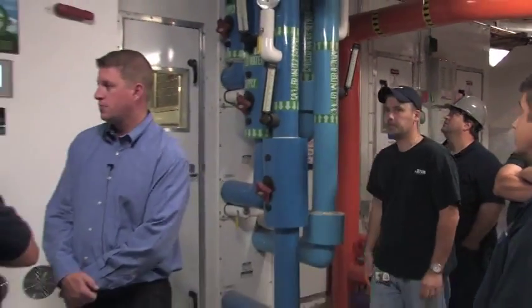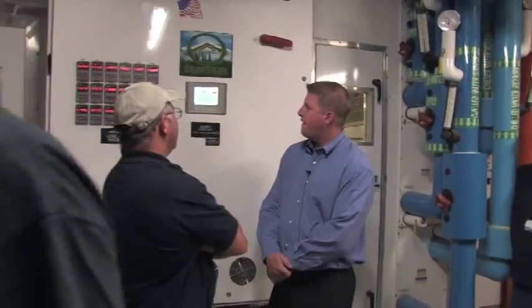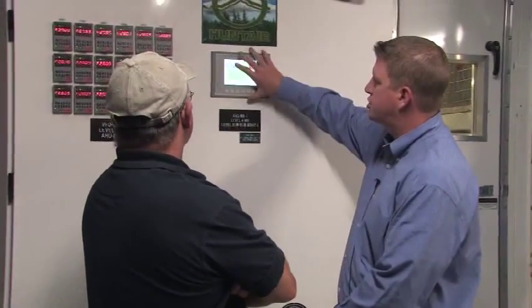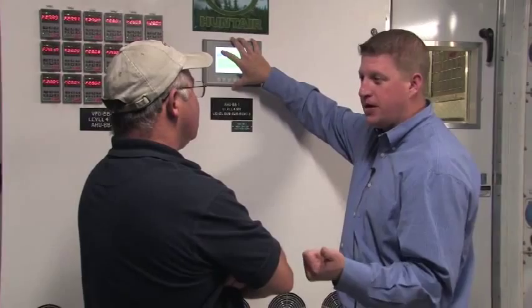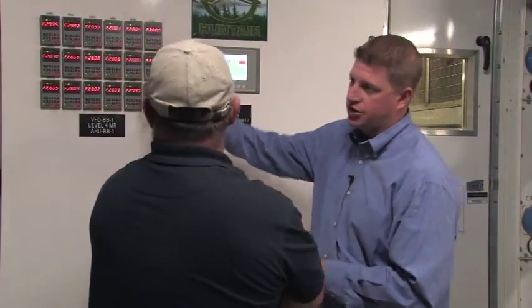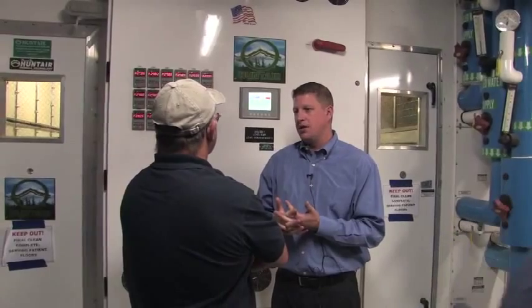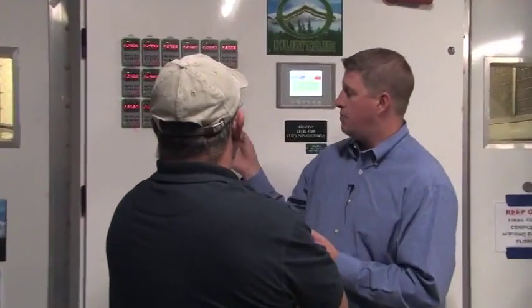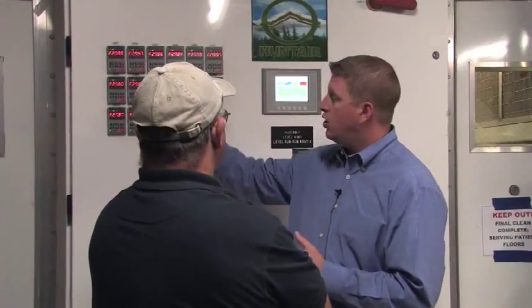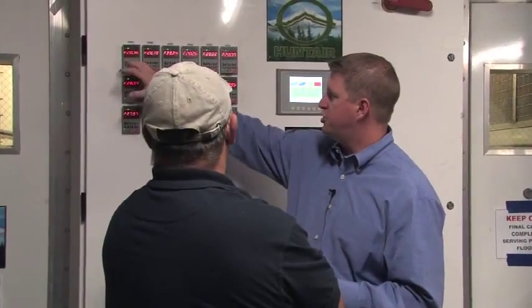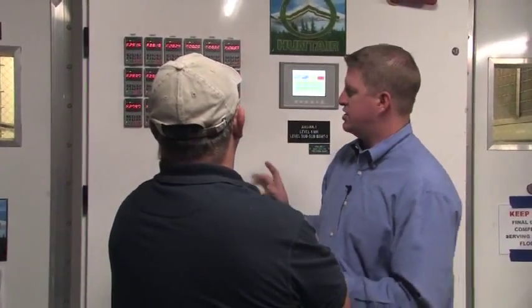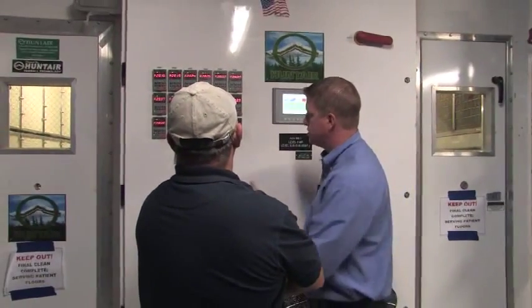So you really never have to touch these things at all. If you had a catastrophic failure of this touch screen and your BMS, you could get down to a level to control the drives individually. And if you ever got to that level, you'd probably be at a point where you'd have an EPA technician on site. And if you wanted to, I could walk you through it over the phone. You would set all the VFDs to the same hertz, not randomly pick them, because you want a harmonic balance, not an imbalance. Then you'd set them all to the same hertz, and then you'd hit run, run, run, run, run. And I can go through that with you right now, just to give you a crash course.